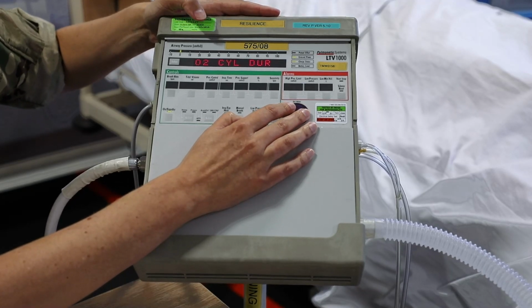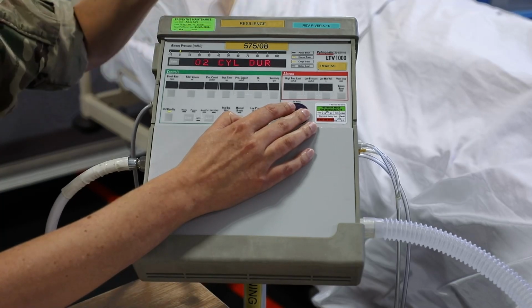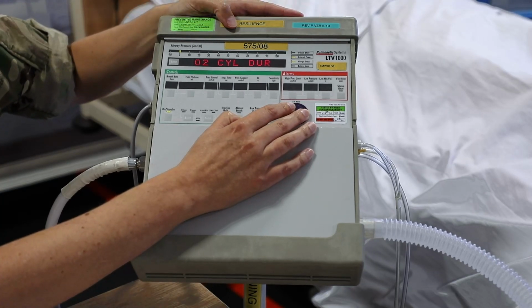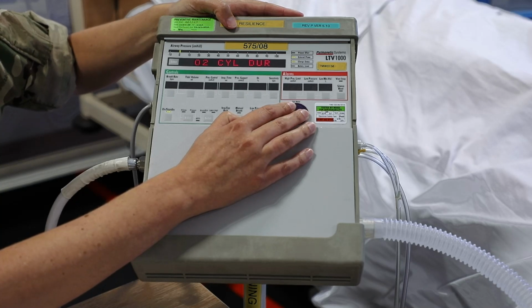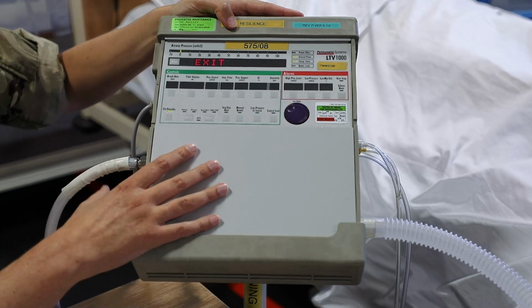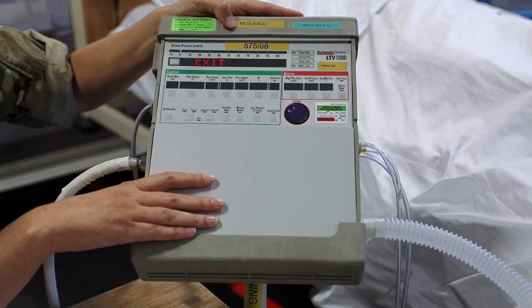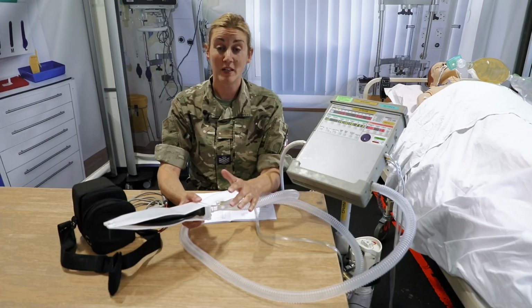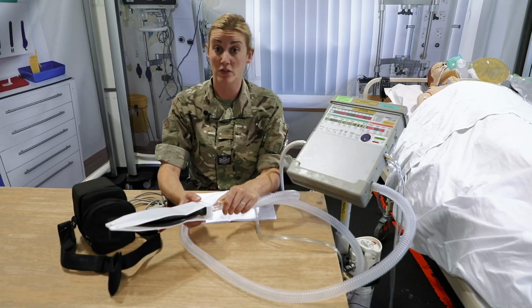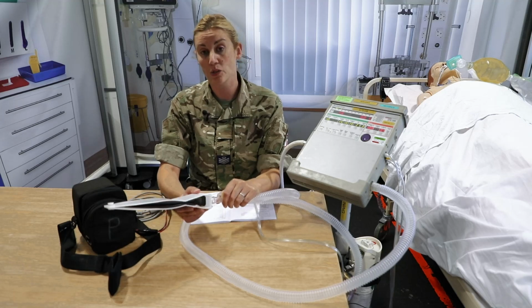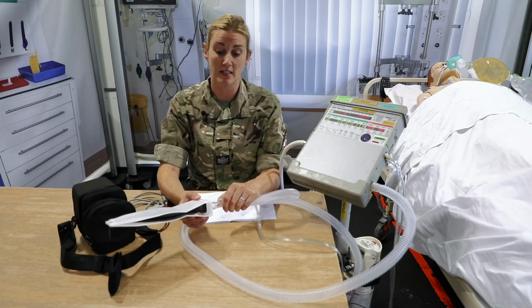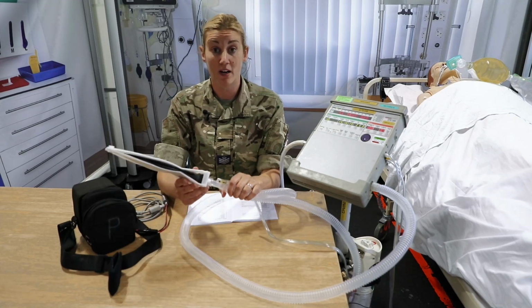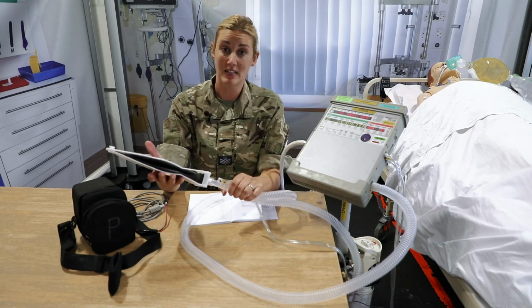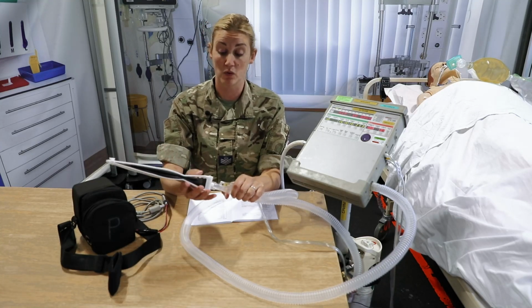O2 cylinder doesn't work anymore because it's based on the old steel cylinders, so it doesn't work for the double-skinned white cylinders that we use now. And then scroll through to the exit. Once you've been through all those functional checks and you've been through those three menus, we're going to move into our real-time transducer data. This is going to require the test lung because the LTV is going to be ventilating, so just get that connected up to the Y connector.